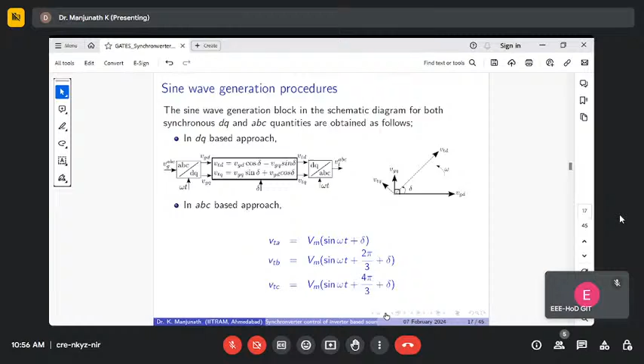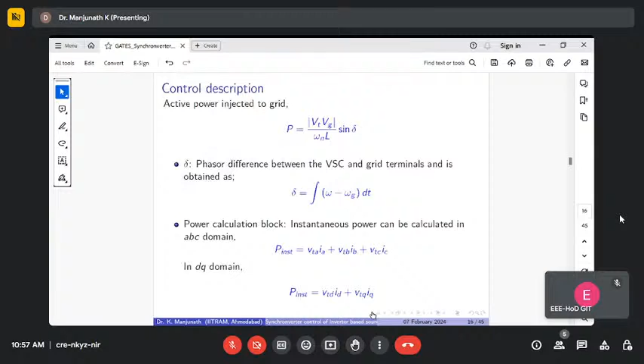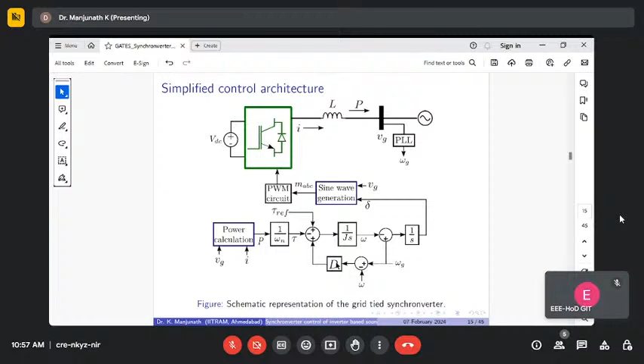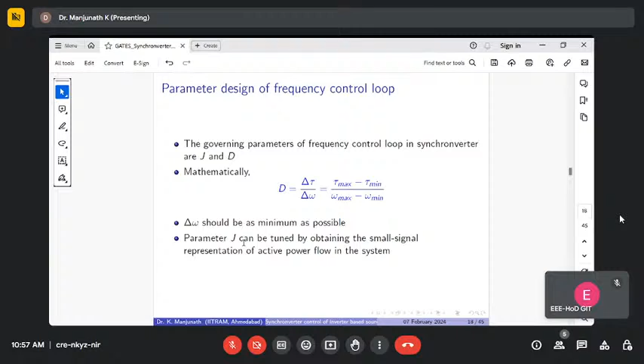Now coming to parameter design, which is very important. If you look at the control representation in the frequency control loop, there are two control parameters: one is J, another one is D. J being moment of inertia and D is droop related to torque and omega. Here droop is computed using mismatch in torque upon mismatch in frequency. We know very well that we are maintaining a very compact band, so frequency mismatch has very less margin. So delta omega should be as minimum as possible, and parameter J can be obtained using any linear analysis.